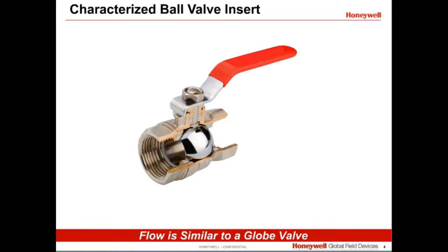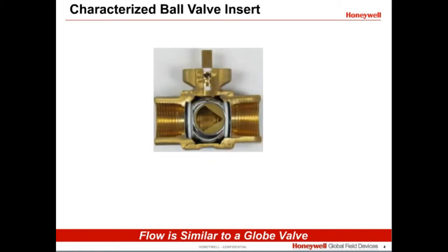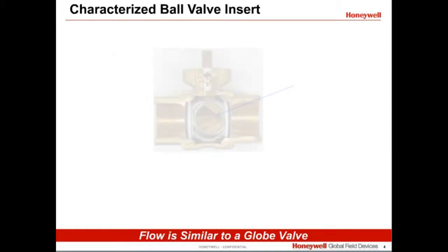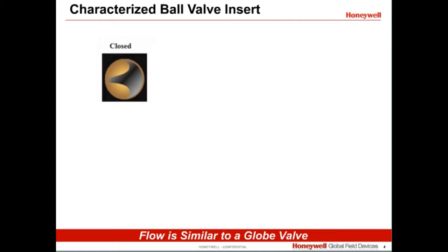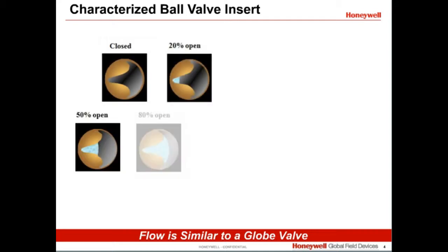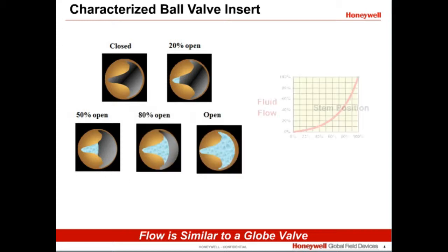Traditionally, ball valves were two-position, open or closed. Modern control ball valves include a characterized insert that makes them perform more like a globe valve. These inserts are pressed into the ball and give the valve a characterized flow ideal for modulating control applications. As a ball valve with a characterized insert opens, the flow rate increases by a certain percentage. This is called equal percentage flow.